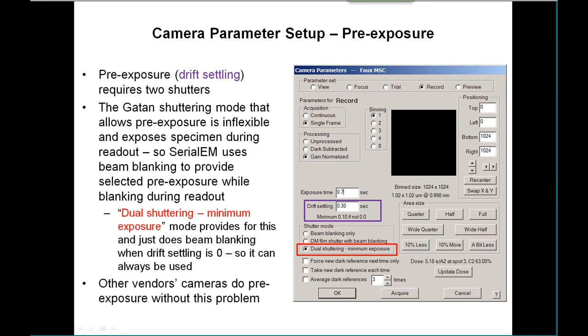Long ago, I developed this method of using beam blanking both to provide the pre-exposure before the actual exposure that you want and also to provide blanking during readout. If you have drift settling and have this dual shuttering minimum exposure selected, it will use that method and provide just the amount of exposure that's needed.